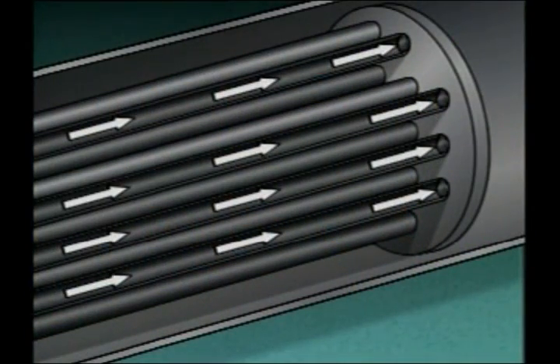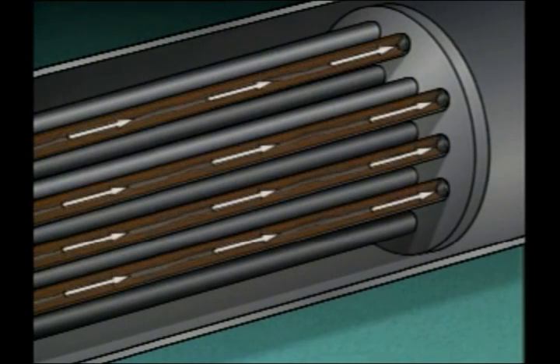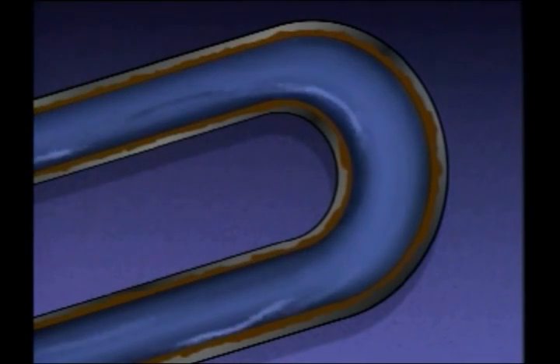Many factors can lead to abnormal conditions in a heat exchanger. Some common problems are scale, corrosion, tube leakage, and tube blockage. Scale is a buildup of solid impurities on the inside of a tube wall; it acts as an insulator, reducing the tube's ability to transfer heat. Another problem, corrosion, can also form on tube surfaces and act as an insulating layer, which can also lead to heat transfer problems. In addition, corrosion can eat away and weaken tube metal.